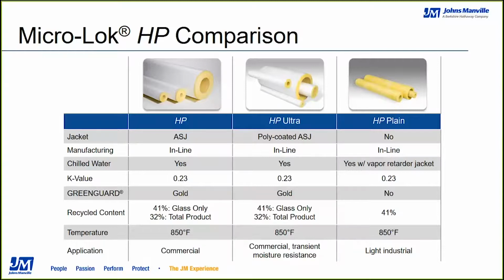Micro-Lok HP Ultra takes the same core fiberglass and utilizes a polyvinyl coated paper jacket, and Micro-Lok HP Plain is provided without a jacket to be used with other jackets such as aluminum or PVC, as well as being a great option for nesting to achieve larger insulation thicknesses. As you can see, the HP and HP Ultra contain recycled content and have a maximum startup temperature of 850 degrees, typically with an operating temperature of 450 degrees or less. The applications vary from commercial to light industrial, and all are produced in line in our factory in Defiance, Ohio.